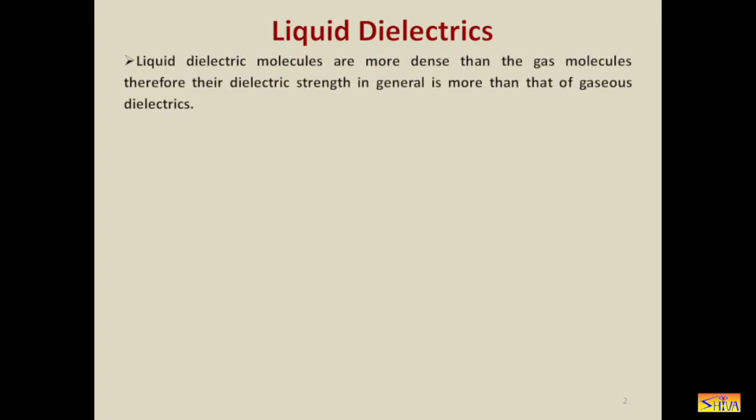Liquid dielectric molecules are more dense than the gas molecules. Therefore, their dielectric strength in general is more than that of gaseous dielectrics. And it is observed that the dielectric strength is more than 100 kV per centimeter. If you remember, the dielectric strength of the air is 30 kV per centimeter, and in general, the dielectric strength of liquid dielectric is more than 100 kV per centimeter. Now let us see where are the applications of liquid dielectrics.